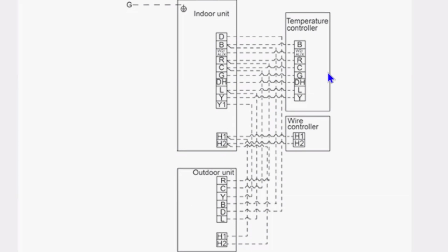and that's where it gives you the error code on the outdoor unit. Now, depending on what thermostat you use, you also see this L terminal going from there to the temperature controller. Be very careful, because some thermostats, if they have an L terminal, that's an output, sometimes it's a 24-volt input. You need to make sure it is a 24-volt input, because we're going to send 24 volts out on L if it's an alarm. So if you have a thermostat that's trying to put out 24 volts, that doesn't work, and you could end up damaging either the board in the air handler or the thermostat itself. So be very careful in how you do that, okay? So if you're not sure, I would just tell you don't hook it up. When it goes into alarm, the code will be shown on the outdoor unit. You will also hear the audible alarm on the indoor unit.